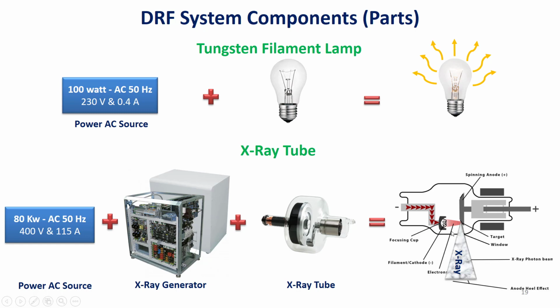Also, we should know that only 1% of the X-ray tube power generates X-ray radiation, whereas the rest of the power will be wasted as heat. Thus, we also need to cool the anode side using a motor to avoid its damage. In this case, we use a rotating anode. Thus, all these functions are supported by the X-ray generator, which also supports other functions related to the tilting table, the operator console, and other DRF system parts.